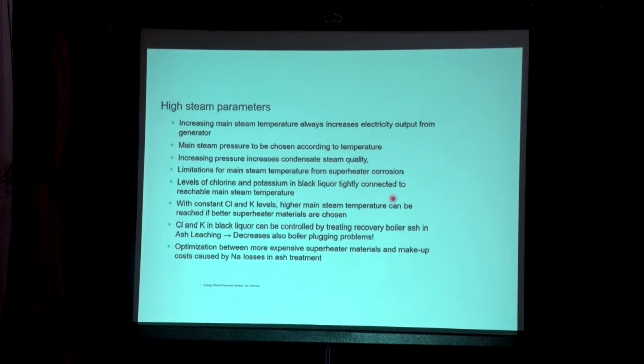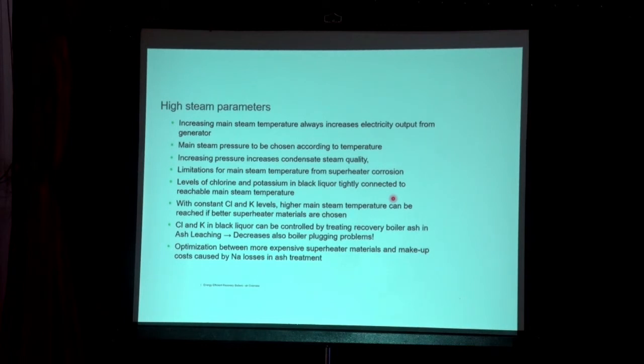For high steam parameters, we operate at more than 90 bar, and up to 110 bar, with temperatures from 480°C and above — 490, 500, or 515°C — depending on the turbine supplier requirements. This increases electricity output. However, a key limitation is superheater corrosion risk at high temperatures due to high chlorine content in the black liquor ash. Chlorine and potassium levels in the black liquor must be carefully controlled when operating at high pressure and temperature.